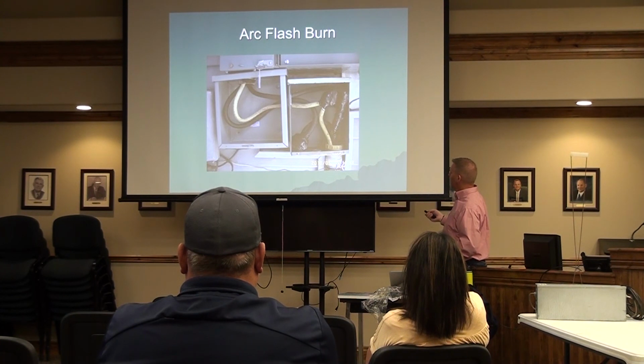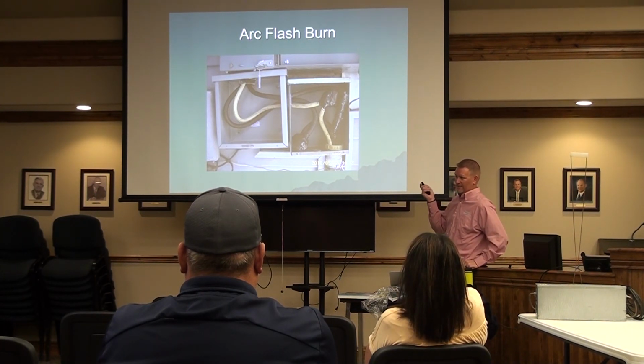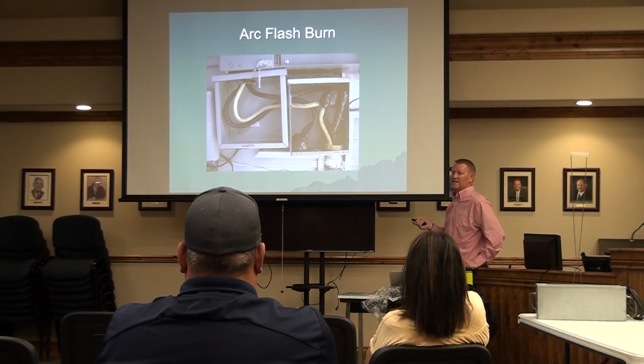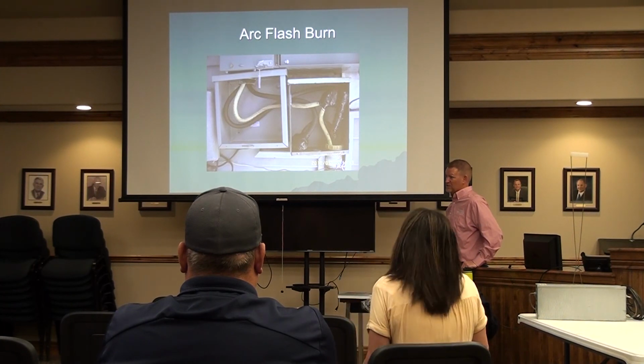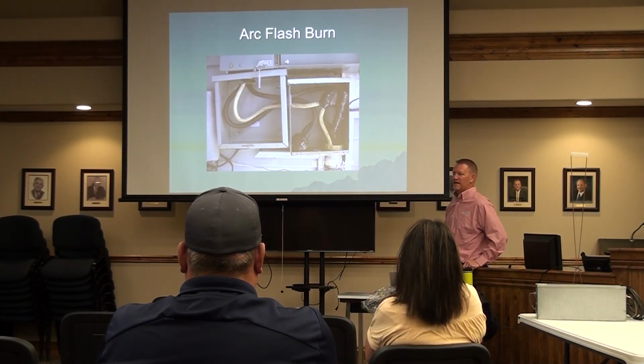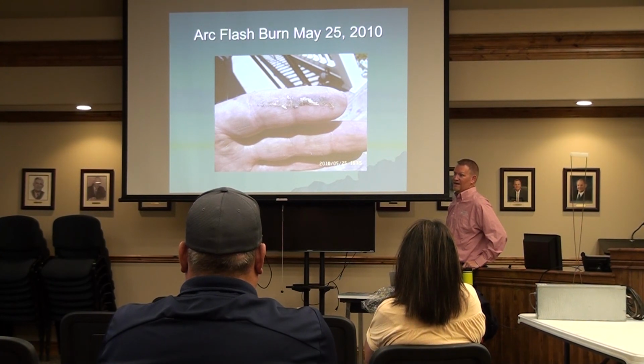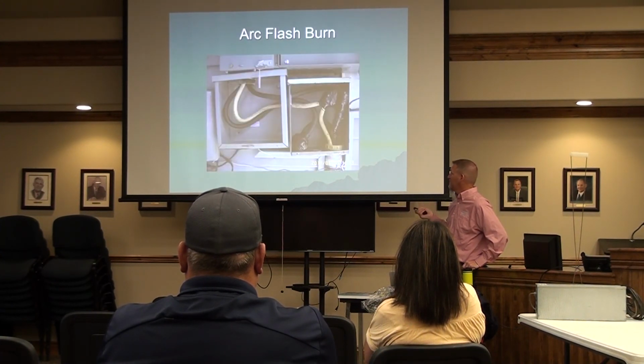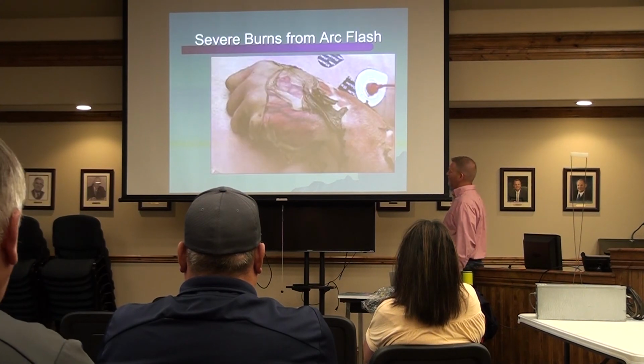Now, if you look, this is probably coming from the utility. I don't know, I can't see it, can't really see what's going on, but this is the meter side typically. So what this tells me is this is even a worse day because there's no breaker ahead of this. The breakers are in here. So if you pulled anything out of here, yeah, you'd have a 20 amp circuit. Right here, this is all at the mercy of the fuse in the transformer at the utility, which is huge. It'll burn right through that panel, guaranteed, it won't even trip that fuse. In fact, he's lucky that's all that it was. That's a lucky day, but it didn't happen even worse. And the electrician that did all this, he's no longer licensed in Idaho. It's done and done, they pulled his license. I was in the board meeting when they pulled it.